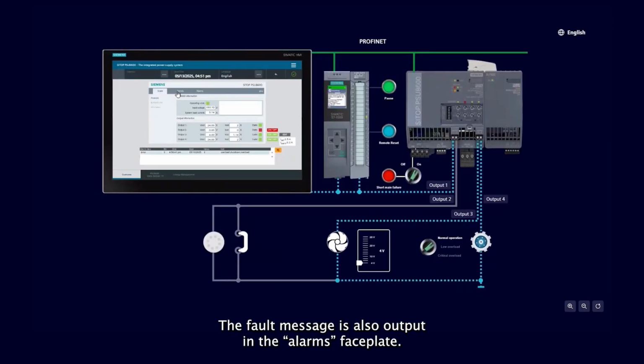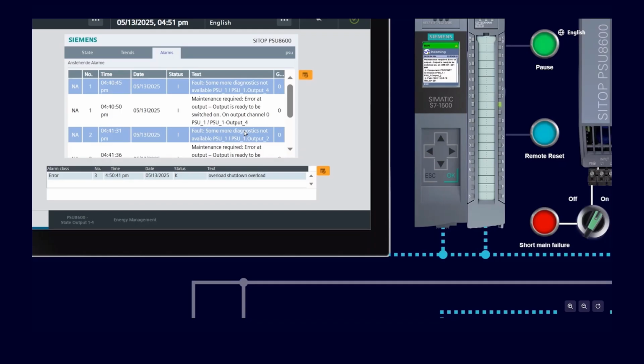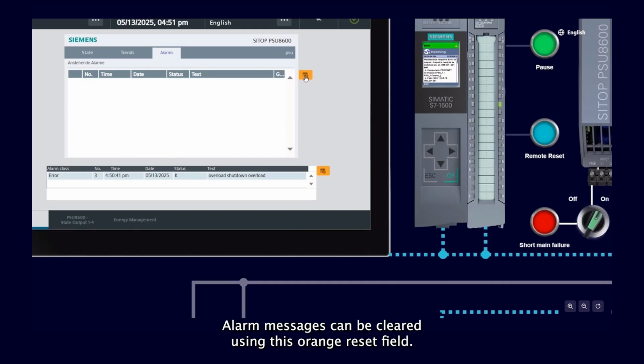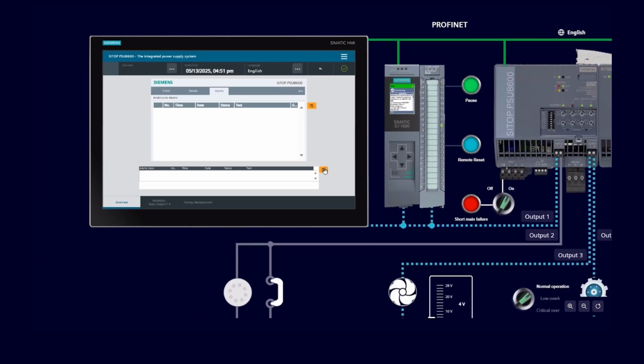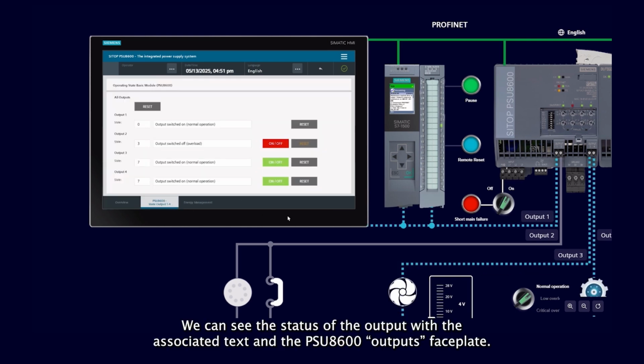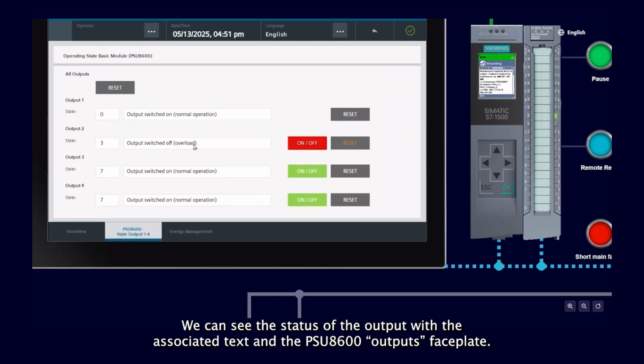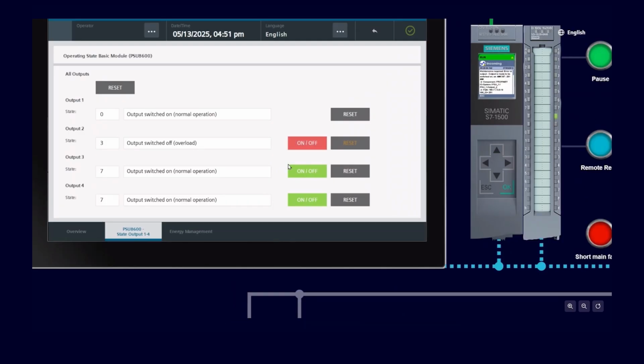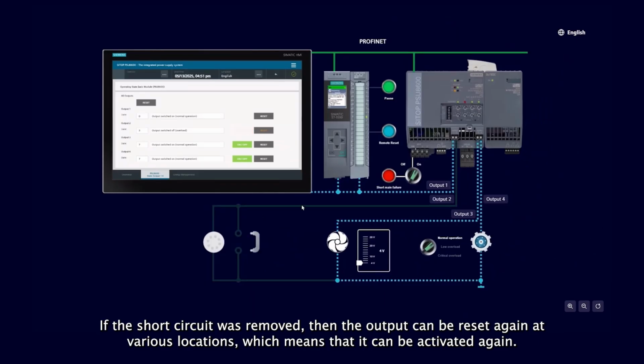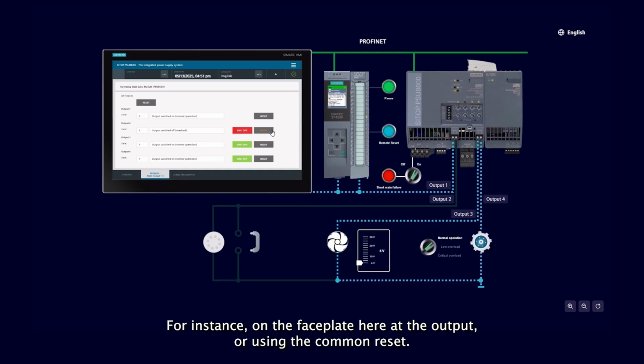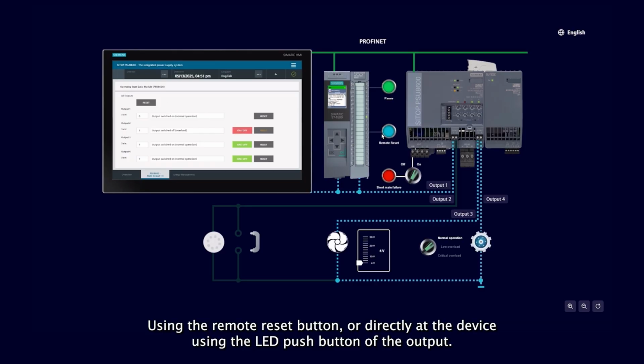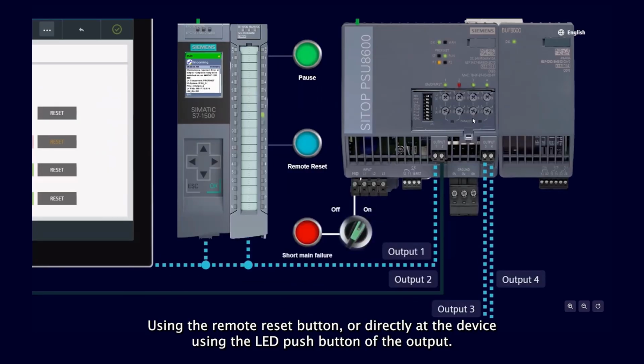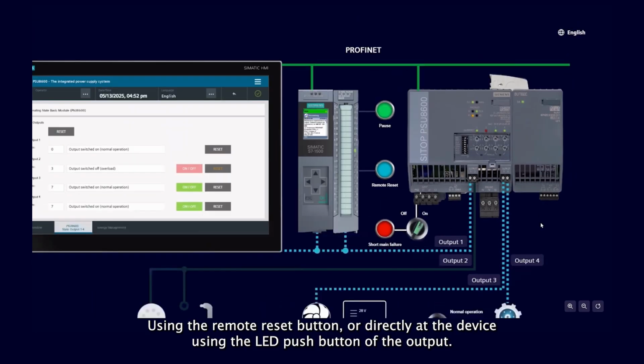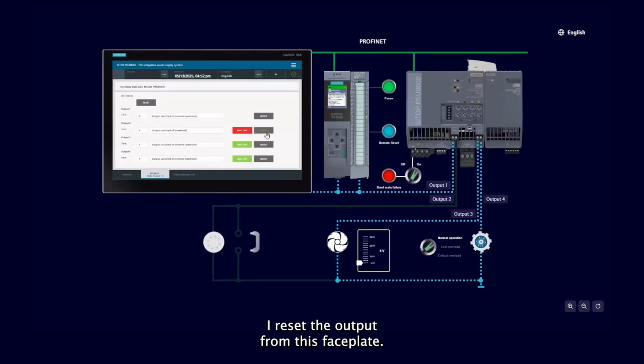The fault message is also output in the alarms faceplate. Alarm messages can be cleared using this orange reset field. We can see the status of the output with the associated text in the PSU8600 outputs faceplate. If the short circuit was removed, then the output can be reset again at various locations, which means that it can be activated again. For instance, on the faceplate here at the output, using the common reset, using the remote reset button, or directly at the device using the LED push button of the output. I reset the output from this faceplate.